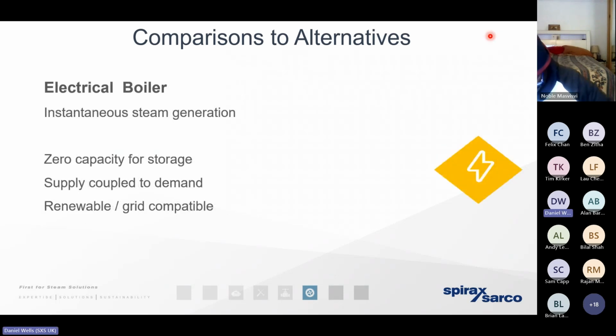An electric steam boiler, great as we know, it produces steam very, very quickly. We can use electricity. What it can't do is store that thermal energy, which means if we want to rely on an electric boiler, the risk is it's going to be sized on that instantaneous peak demand. It's going to be oversized for the vast majority of its operational condition. And that may mean that we need to overhaul the electrical infrastructure that's available locally to such a point where it's not going to be financially viable.